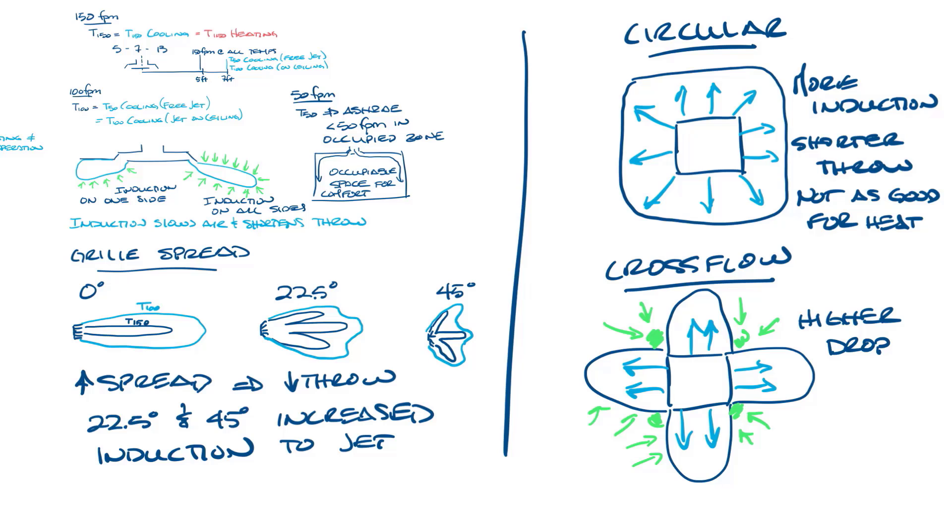As supply air comes out of the cross flow diffuser, room air is being induced into these corners. And since there's no airflow coming out of the corner, the dirt is induced and can collect in the corners. Circular pattern diffusers don't usually have smudging since their air flows from all around the diffuser.